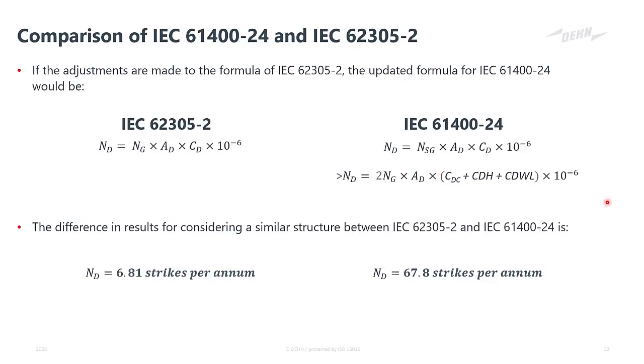Now I did a comparison. If I take the same structure or the same wind turbine, which is 200 meters tall in an area with a lightning flash density of about 5, in a mountainous area with a high elevation, if I use the old method that's not adjusted, you can see the number of strikes would have been calculated as 6.8 strikes per annum. If I use the method from 61400-24, that value is increased to 67 or 68 strikes per annum to a wind turbine.